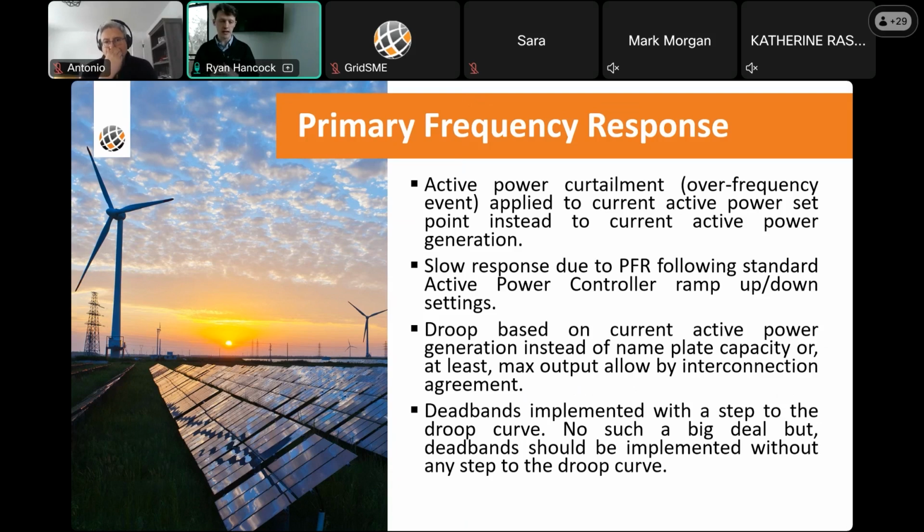Another common error that we see is slow responses with the ramp up and ramp down settings. The difficulty of addressing this comes from the fact that there aren't a lot of standards in place that truly dictate this, especially in a way that we believe is actually useful for a lot of projects. The problem that we have is defining how fast slow needs to be.